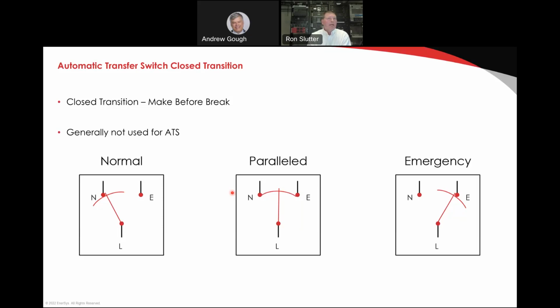This means it's make before break. So when this particular bar moves, the handle here on this segment moves for a short period of time, usually less than 100 milliseconds, it joins the two sources together and then moves off of that to one source, to the other source. So going from normal to emergency, it will hit both at the same time, and then it will finally move off of the old source.